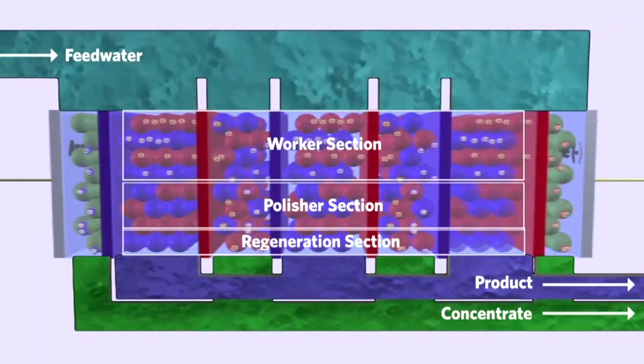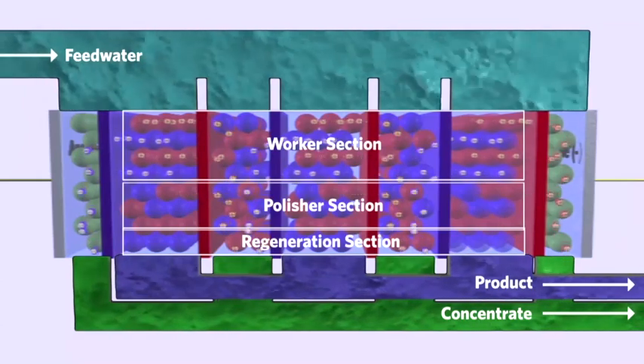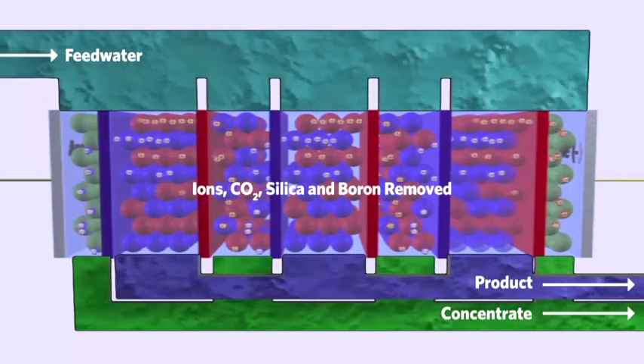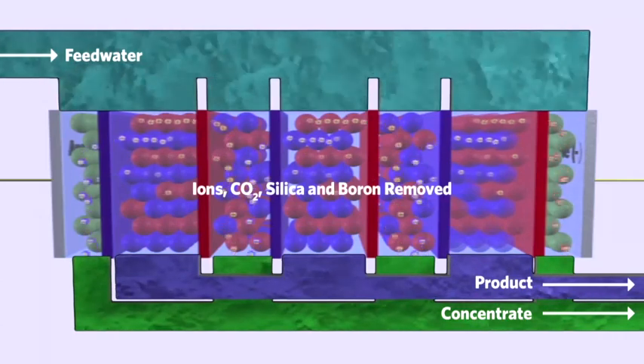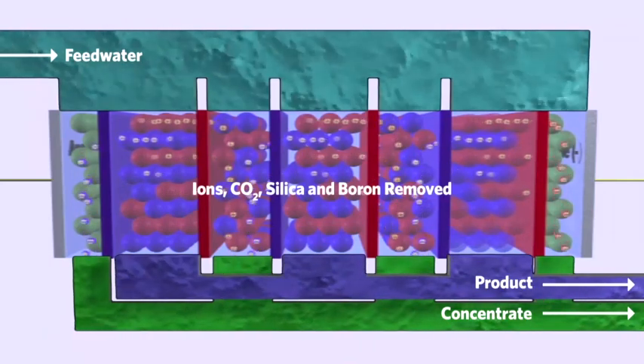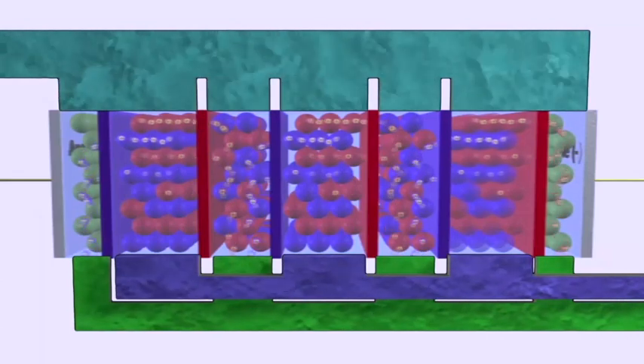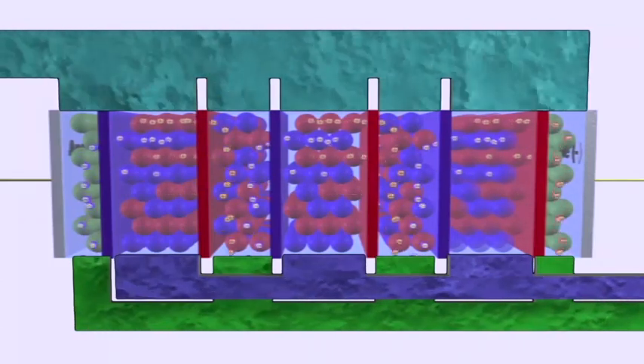And IonPure CEDI systems are more effective than other electrodeionization systems when it comes to removing dissolved materials such as salts, acids and bases, as well as weakly ionized materials such as dissolved organics, silica, boron, and carbon dioxide. This continuous regeneration process also eliminates pH shock and greatly extends the life of the resins.